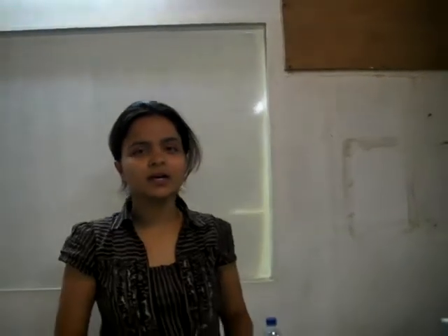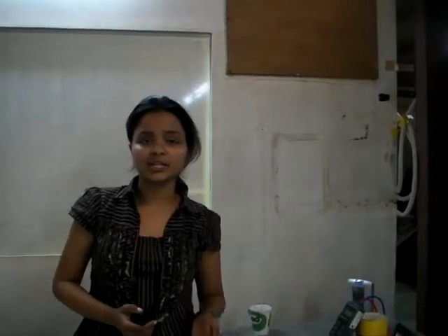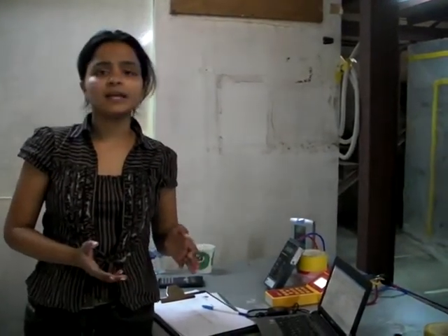Our next step is to increase the fan capacity up to 95% and get the same set of data. We will measure for 5 different fan pressures, the highest pressure being the fan speed of 95% and the lowest being at a fan pressure of 20 pascal. After we finish with the first fan, we will move on with the second and the third fan, and all these data will be collected and will be sent to you. Thank you.